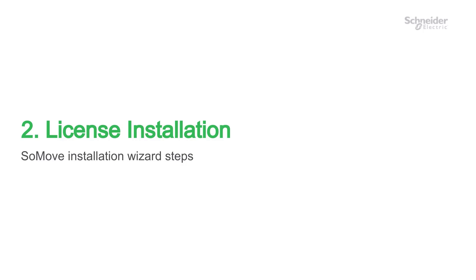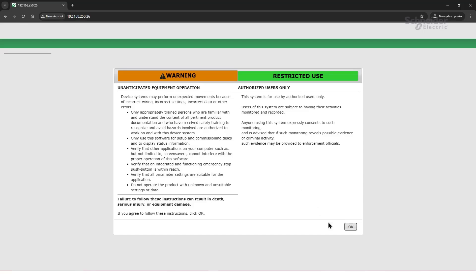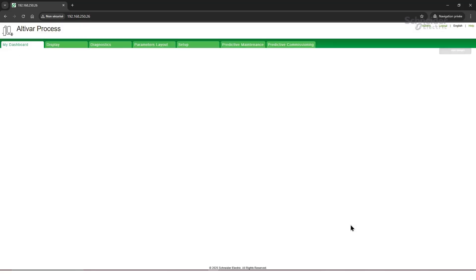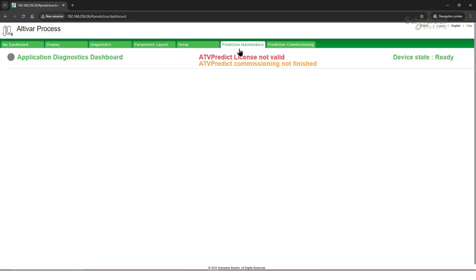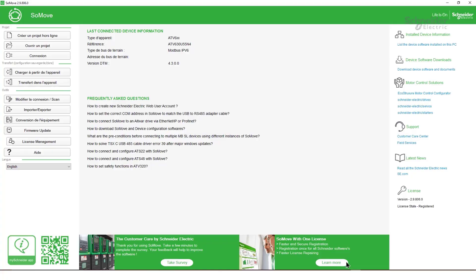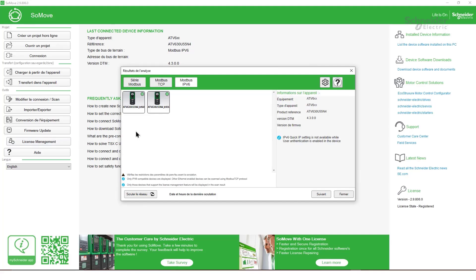Follow these steps in the installation wizard. First, connect to the drive using the built-in web server feature. Navigate through the interface until you reach the Predictive Maintenance section. If you find that the license isn't valid, open SoMove and click the License Management button. The application will show available drives — choose the drive you need and connect.